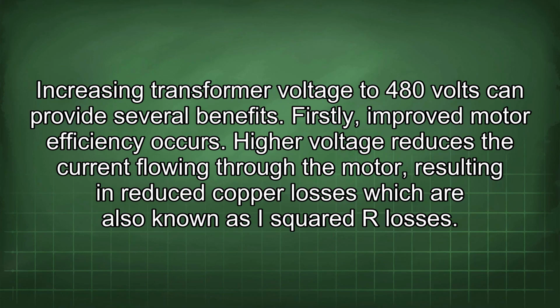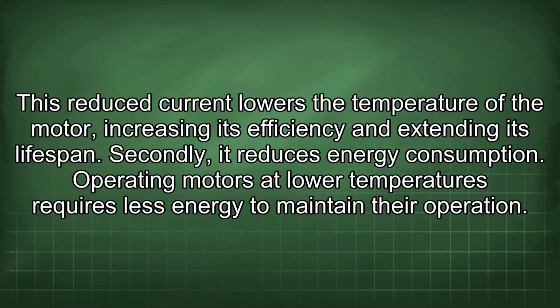Increasing transformer voltage to 480 volts can provide several benefits. Firstly, improved motor efficiency occurs. Higher voltage reduces the current flowing through the motor, resulting in reduced copper losses, which are also known as I²R losses. This reduced current lowers the temperature of the motor, increasing its efficiency and extending its lifespan.